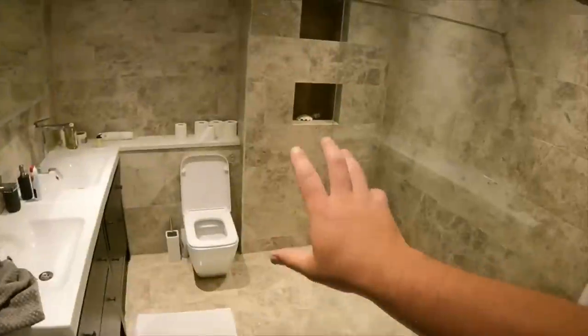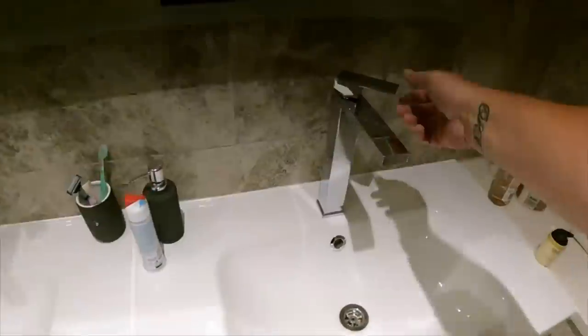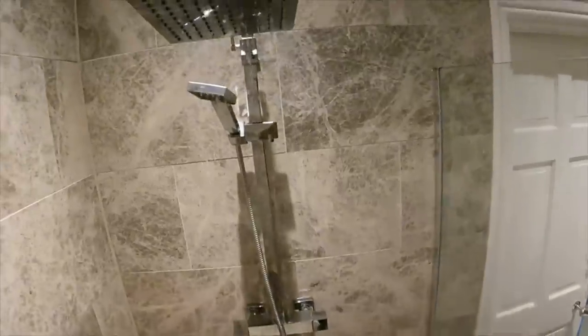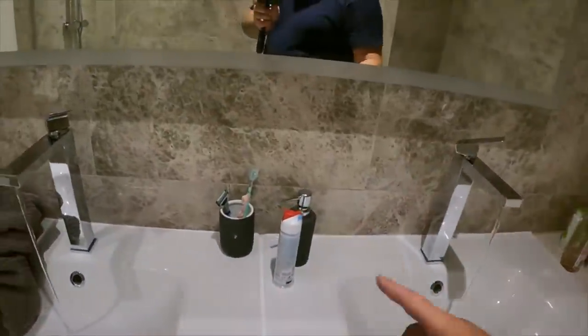I'm going to speak to the landlord about the options and get him to check with Severn Trent the water board to see if there are any known mains issues. The tenants have said it's been like this since they moved in. Ground floor is fine, first floor is pretty much all right, but after that you get this issue. So we're probably looking at an accumulator booster tank going in here — but I'll feedback to the landlord first because that shower is no good at all. I'll quickly show the first floor bathroom as well — same issue with the twin basins completely dropping off.